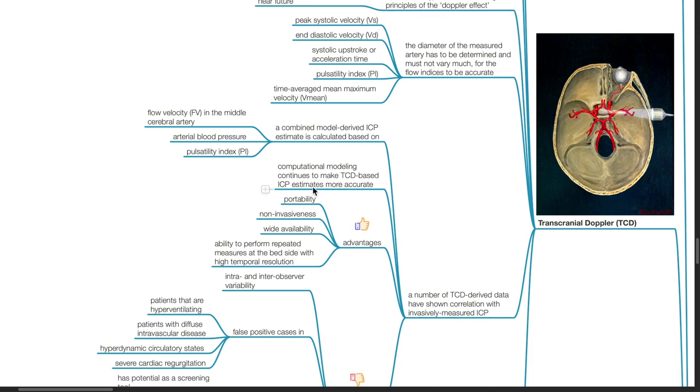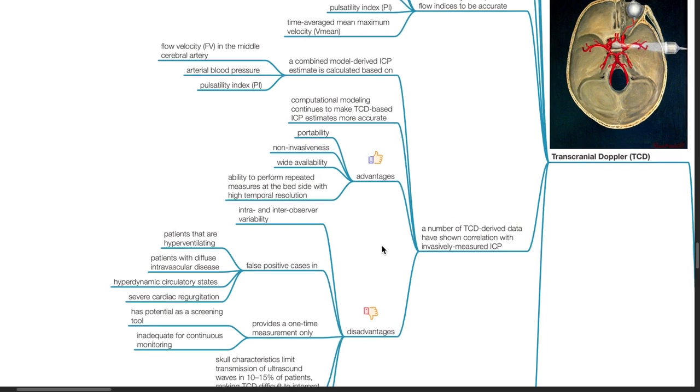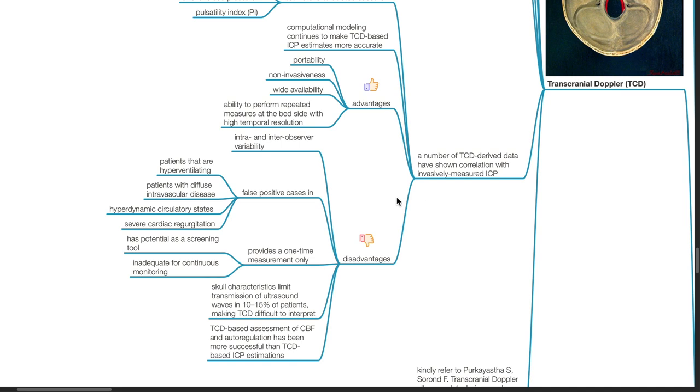A number of TCD derived data have shown correlation with invasively measured ICP. A combined model derived ICP estimate is calculated based on flow velocity in the middle cerebral artery, arterial blood pressure, and pulsatility index. Computational modeling continues to make TCD based ICP estimates more accurate. Advantages: It is portable, non-invasive, widely available, and has ability to perform repeated measures at the bedside with high temporal resolution. Disadvantages: intra and inter-observer variability, false positive cases in patients that are hyperventilating, patients with diffuse intravascular disease, hyperdynamic circulatory states, and severe cardiac regurgitation. It provides a one-time measurement only and has potential as a screening tool but is inadequate for continuous monitoring. Skull characteristics limit transmission of ultrasound waves in 10 to 15% of patients making TCD difficult to interpret. Overall, TCD based assessment of CBF and autoregulation has been more successful than TCD based ICP estimations.